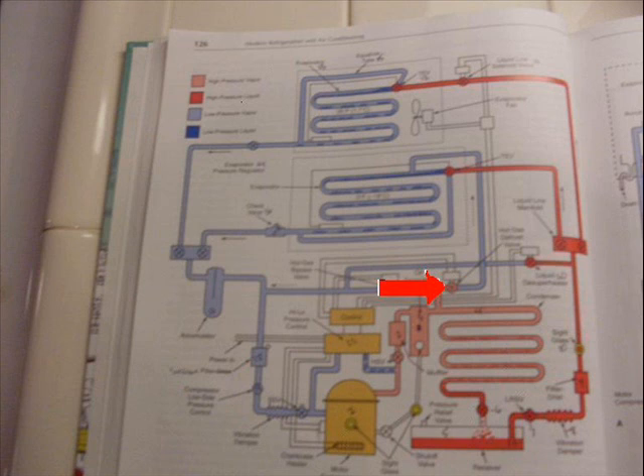Generally, we'll have hot gas two or three times a day for about 20 minutes every eight hours. Now, it's going to vary from system to system, but this is just to give you a feel. So, you'll have hot gas defrost about 20 minutes every eight hours. Now, the hot gas pours into that evaporator after the refrigerant control.